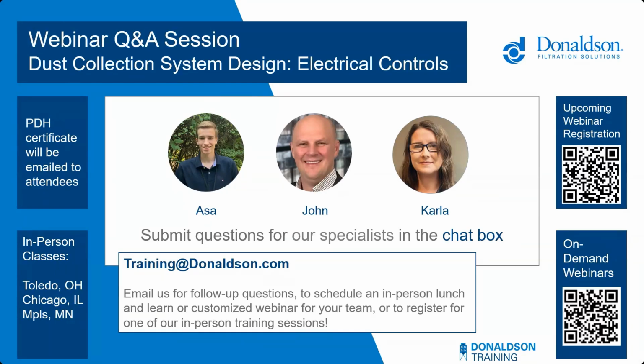All right, our next question. Can you please explain the difference between the timer board and the pulse cleaning controller? I'll take this one too. The timer board is directly what will control the pulsing to the collector. And I get why that's confusing, because the pulse cleaning controller tells the timer board when to turn on and off. So if you have it set to downtime clean, that is cleaning when your collector turns off, the pulse cleaning controller will detect when the collector is turned off and send a signal to the timer board to start cleaning the collector.